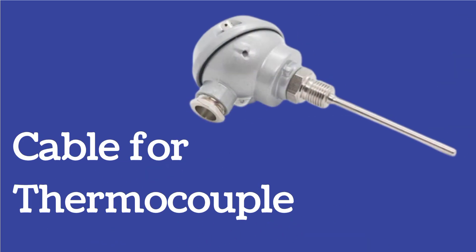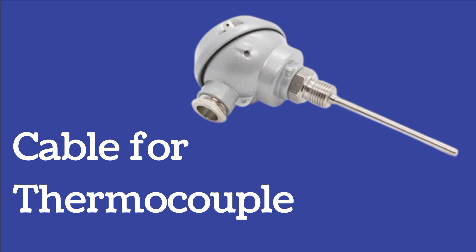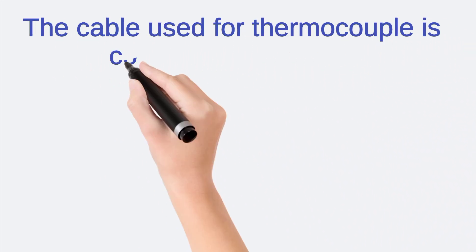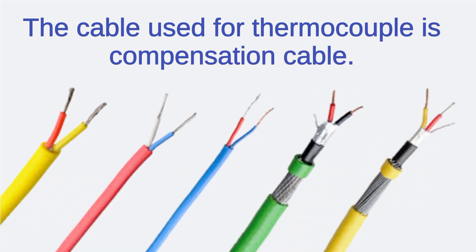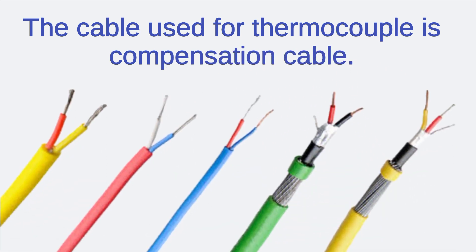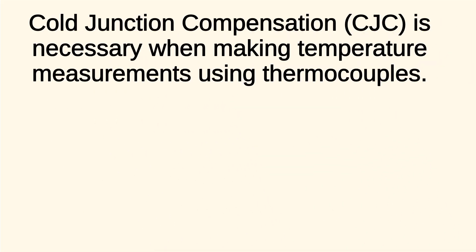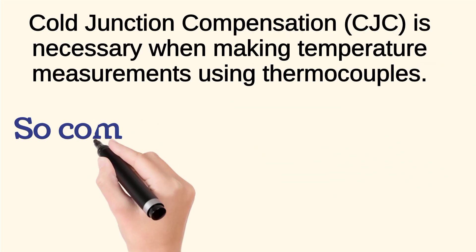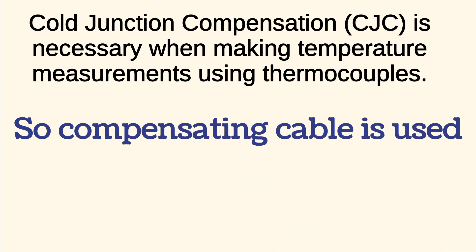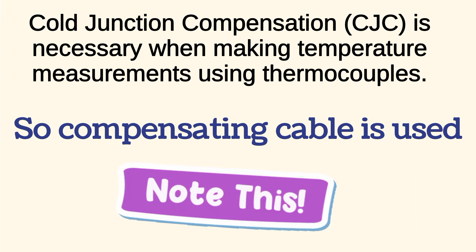Now we will see the cable for thermocouple. The cable used for thermocouple is compensation cable, also known as compensating cable, as shown in the image. When we measure temperature using thermocouples, cold junction compensation is necessary, so a compensating cable is used. This is an important point for interviews, so note it down.